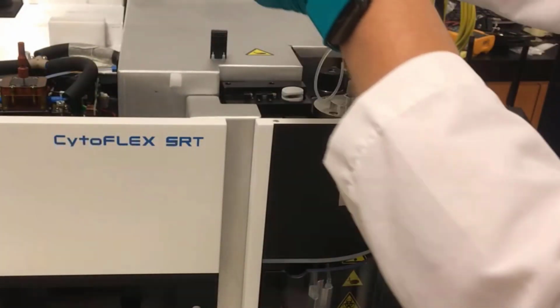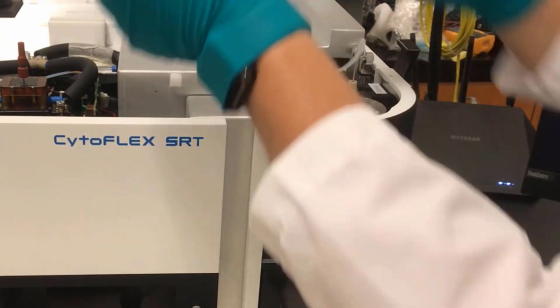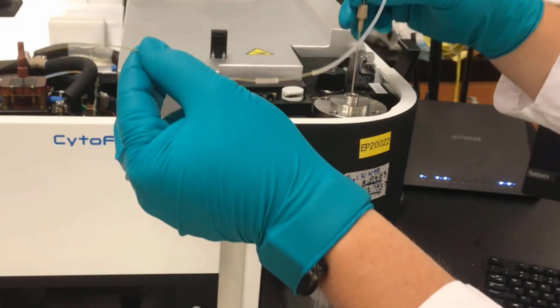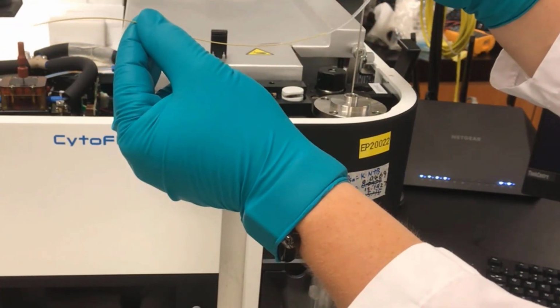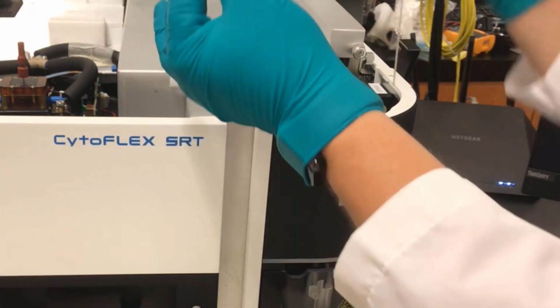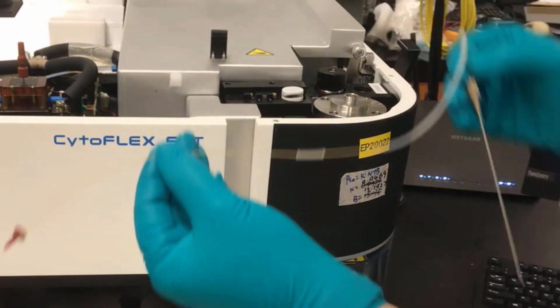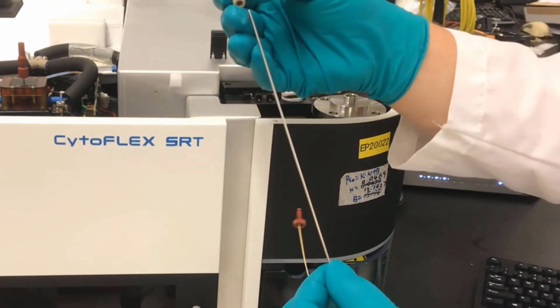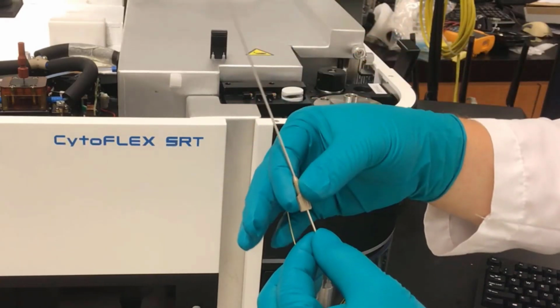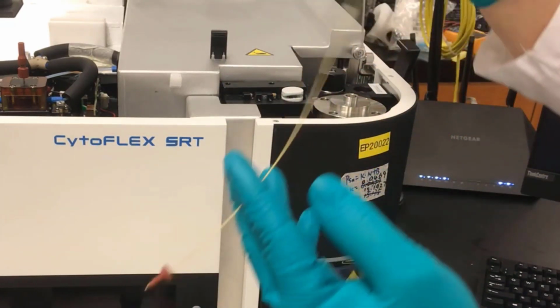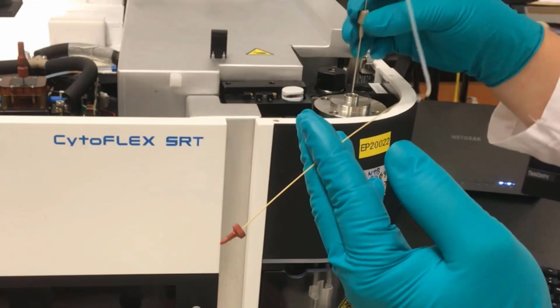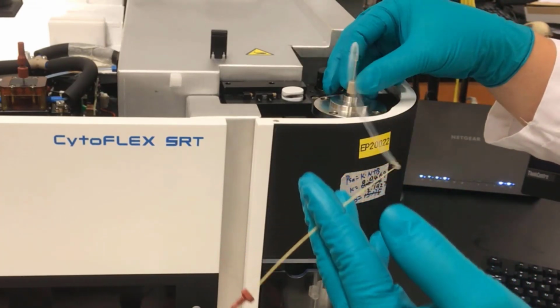Once the fittings and tubing are loose, you can now remove the sample probe. Slowly pull the sample probe upward until it is completely removed from the top plate. Go straight up and avoid bending the probe. To reinstall the sample probe and sample line, feed the new sample probe through the gray finger tight fitting. Feed the sample probe together with the finger tight fitting through the top plate.